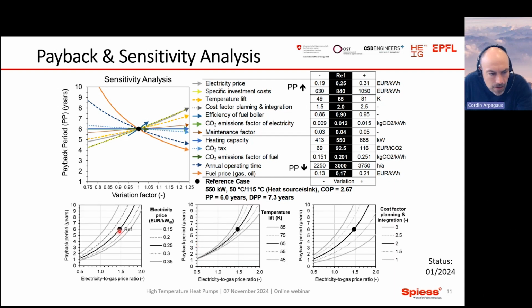From that, we did an additional sensitivity analysis changing only one parameter. Here it is the electricity price. You see here the broader these areas, the more sensitive it is on the payback. The temperature lift is also important. If we increase it, then the COP goes down and the payback time goes up. If you have a higher cost factor for planning and integration, then the payback also goes up. So this is a possible visualization for this case.